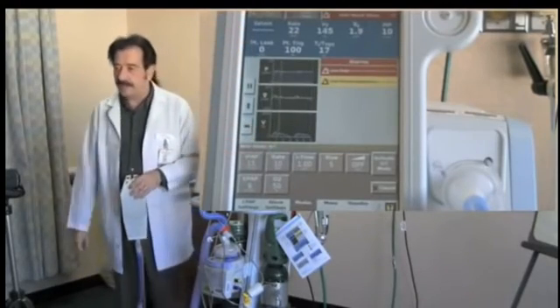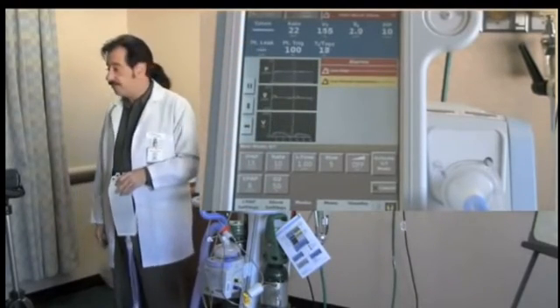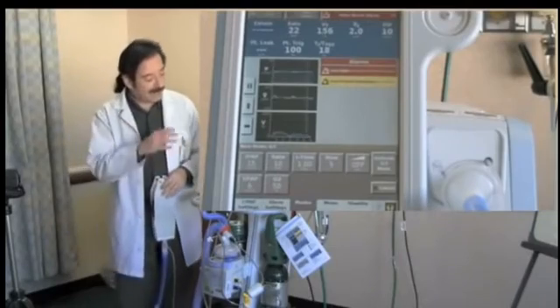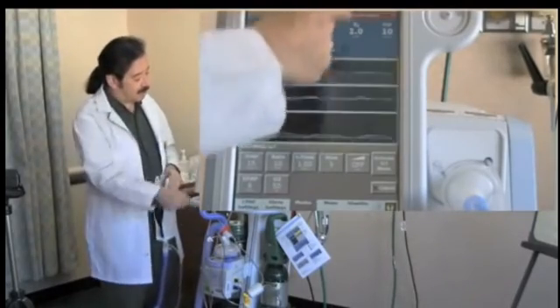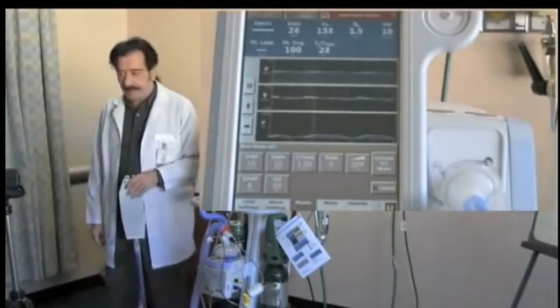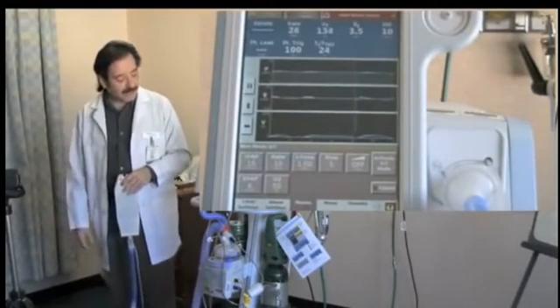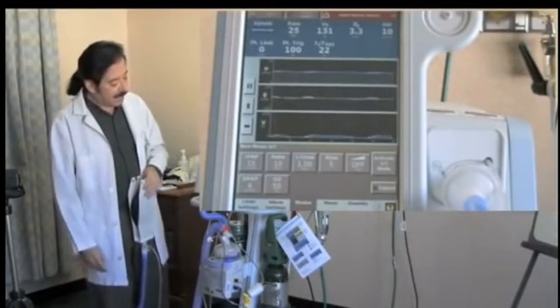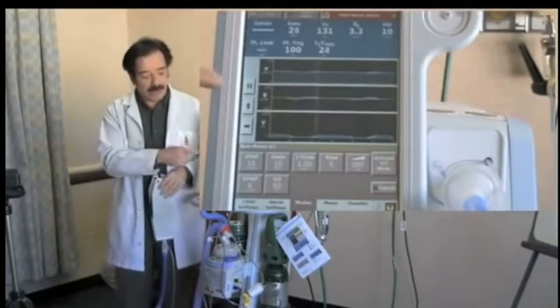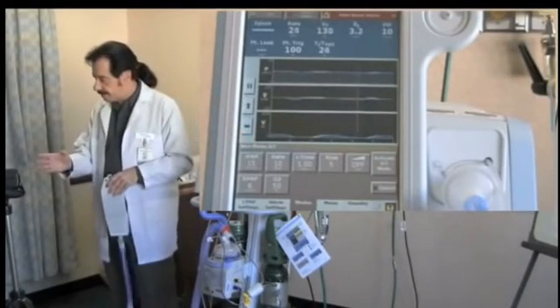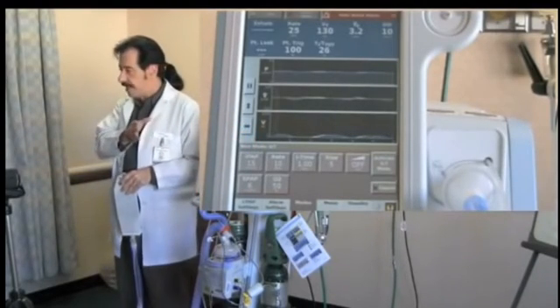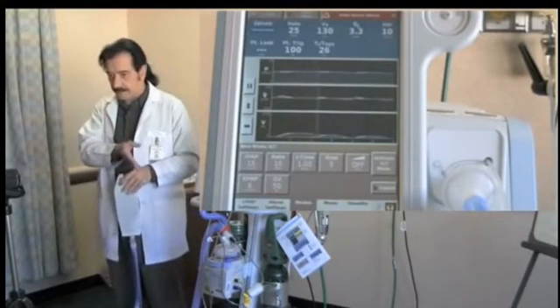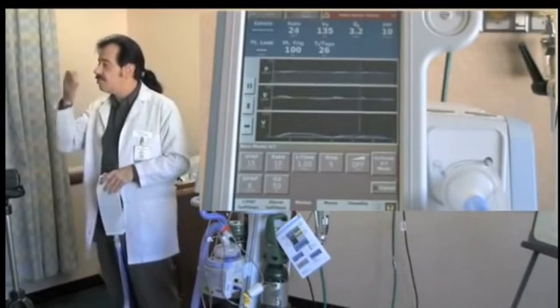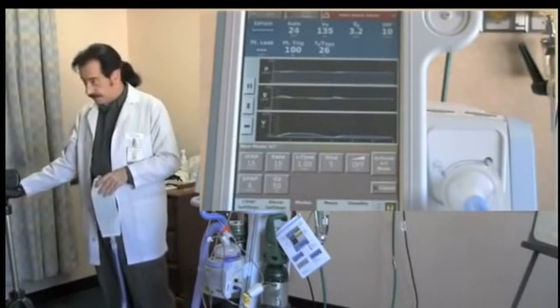Now here I have a rate of 10. The minimum rate I can set is 4. Okay, so the backup rate for adult patients is typically 4, and for pediatric patients can be much higher than that. So it needs to be appropriate for the patient. Now, at a rate of 10, every 6 seconds, the machine looks to see if the patient has triggered a spontaneous breath. If they have not, then the machine will give them a machine breath.